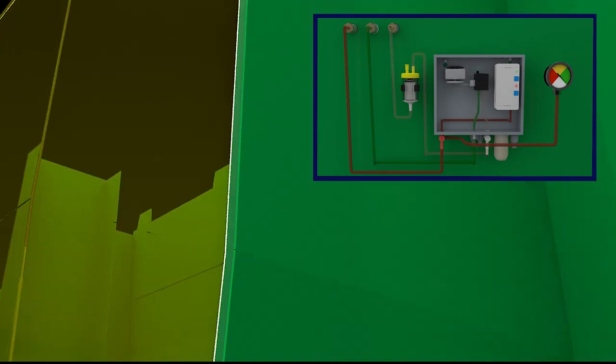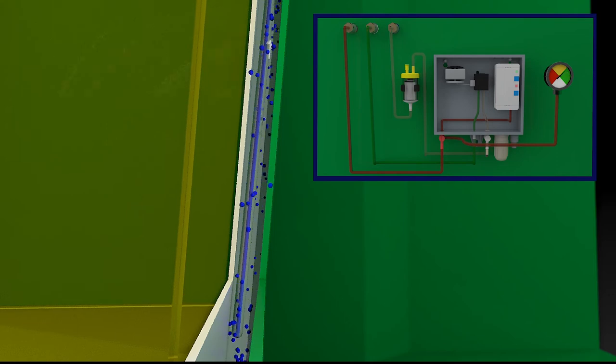If there is a leak in the tank, the negative pressure drops rapidly and can also no longer be sustained by the pump. If the critical limit is reached, the leak detector triggers an alarm.